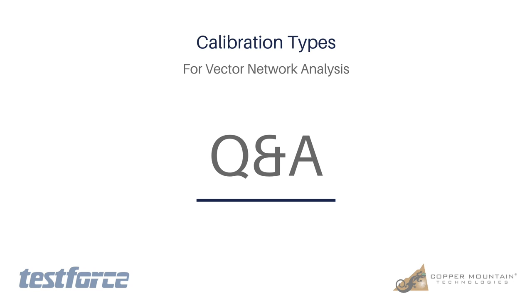Yes, that can be an issue. And generally, I do it all the time, but it's really best to attach the calibration standard and then set it down. And let me show one other thing too, by the way. I can fix it pretty easily. All right.